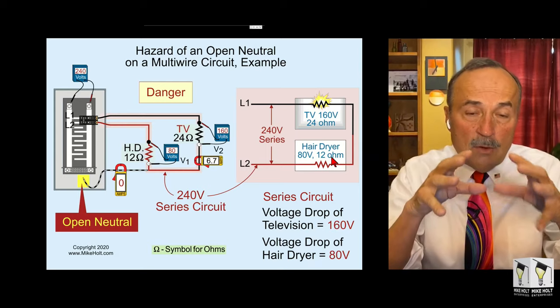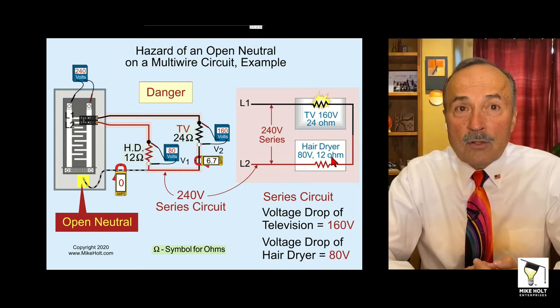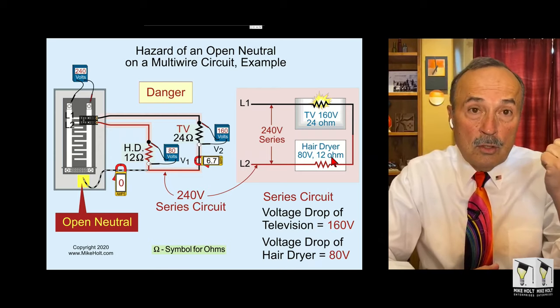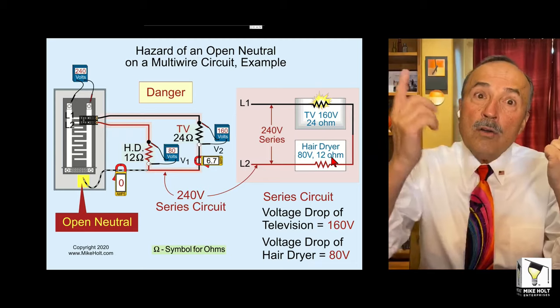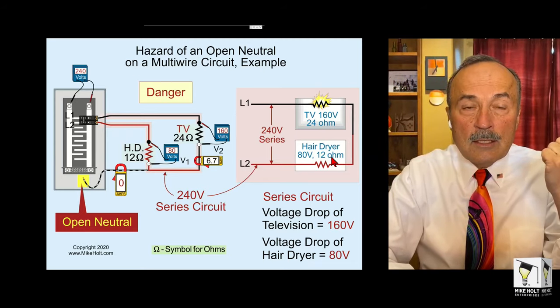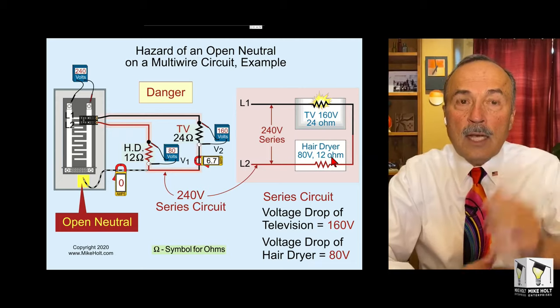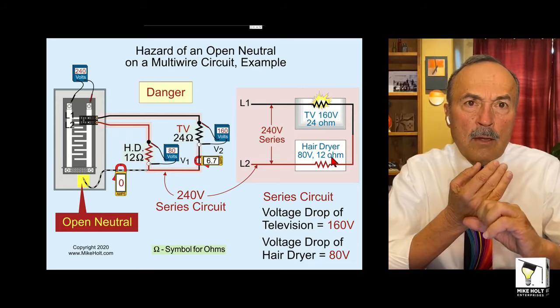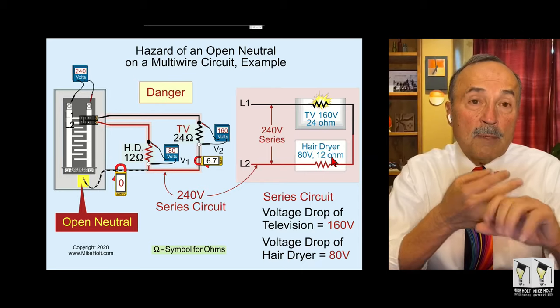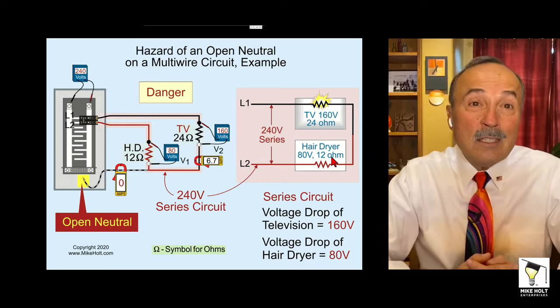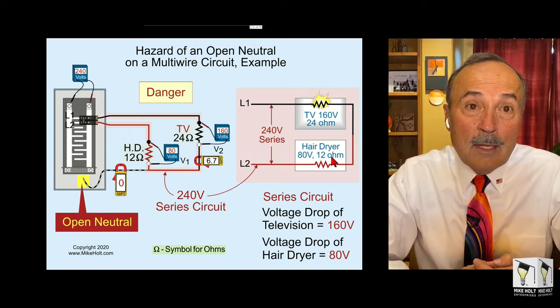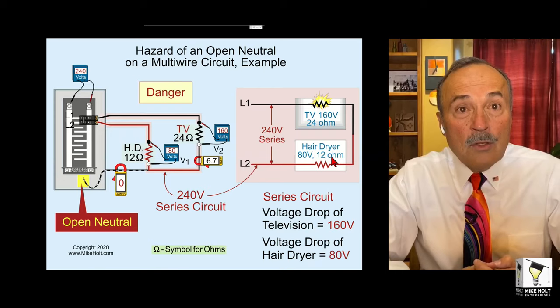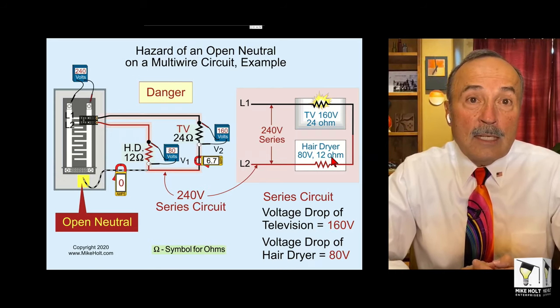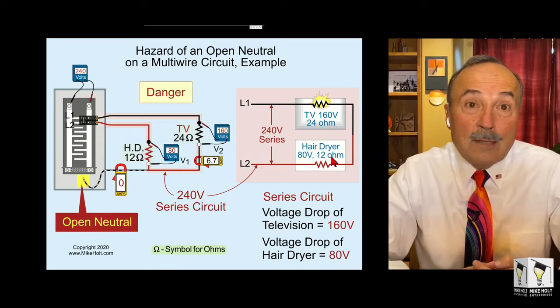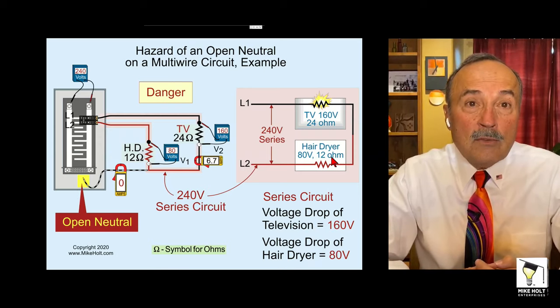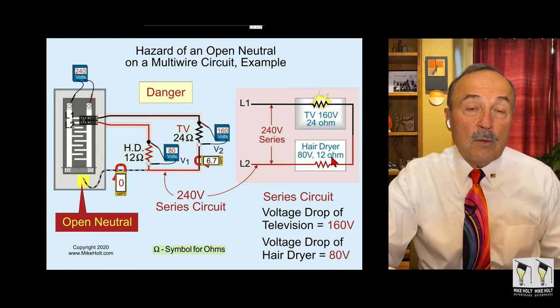I'm not saying that it's a fact because I haven't read it, but I believe that if you were a manufacturer of AFCIs and GFCIs, and the utility loses the neutral, you've already smoked a lot of them, all your phase A AFCIs or GFCIs have gone bad, and then they've kind of realized, okay, besides having internal surge protection, we need some kind of electronic overvoltage protection. But that's a product standard, and you know what? It doesn't even matter to me because I have no control of that. Because if the utility lost a neutral and the device did or did not self-protect and it gets smoked, the utility's going to say, we didn't lose a neutral. We didn't have a problem. Everything is fine. And then it just dies.